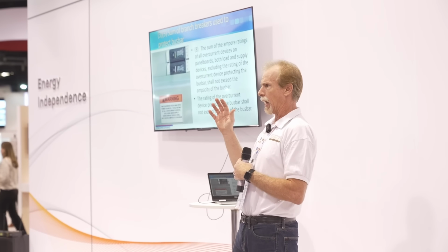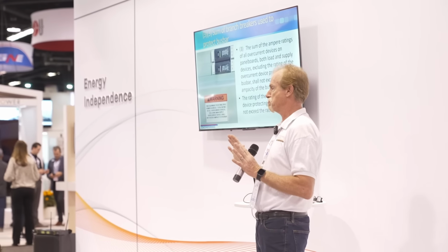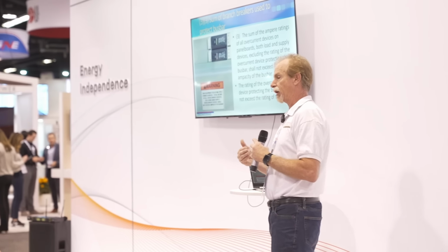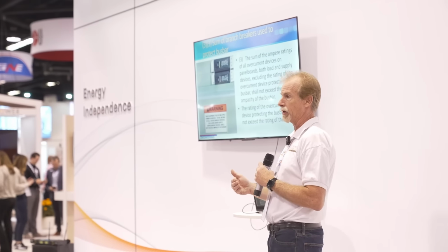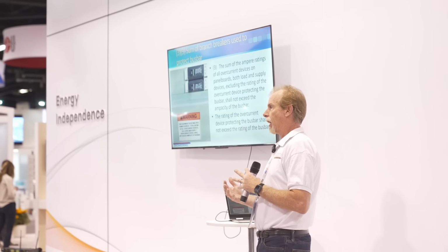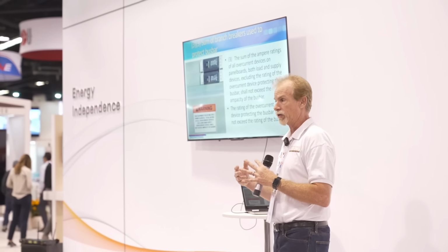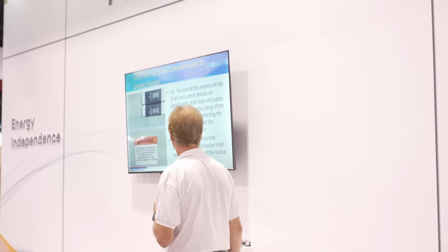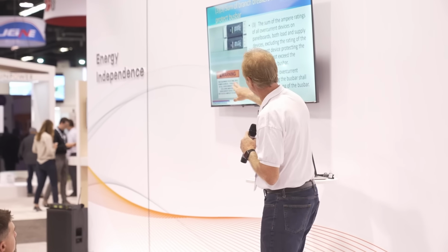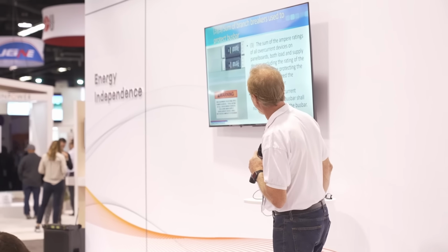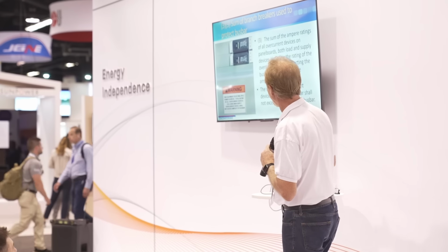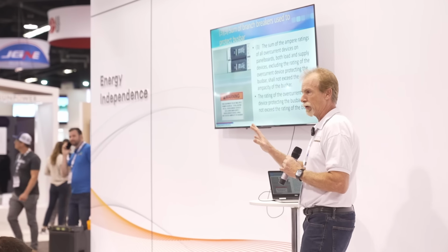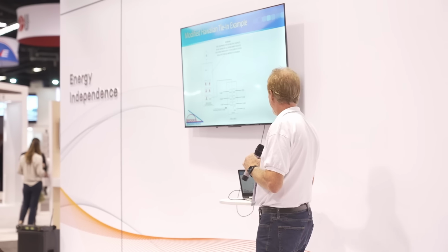It was intended to be a very simple thing. It's like, how much of them are source and how much are loads? We don't care. This is super simple. But it does matter. Yes, it does matter. We're trying to do something very simple, especially for the AHJ, but even for the installer. I call it the take off your shoes, count your toes and fingers, and if you can do that, you can probably do this rule, and it'll work for you every time. And then we have a little sign that says what you have to put on there: Total rating of all overcurrent devices, excluding main supply, cannot exceed the ampacity of the bus bar. Now, when you get into three phase, it gets a little more complicated. We're not going to go into that, but let's just move on.